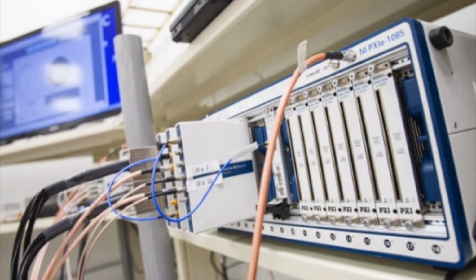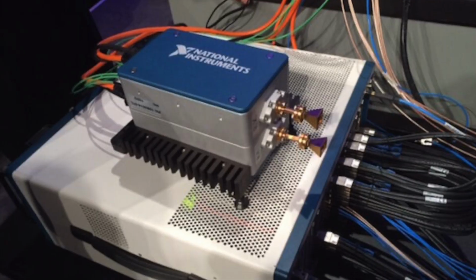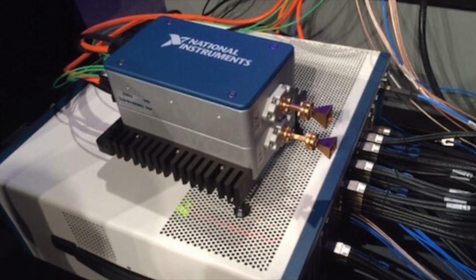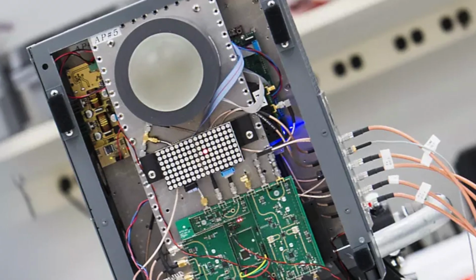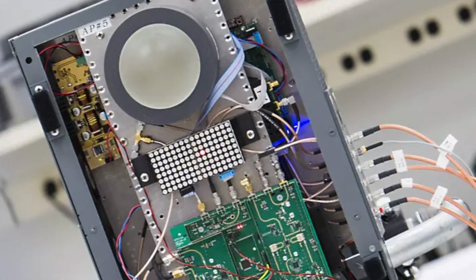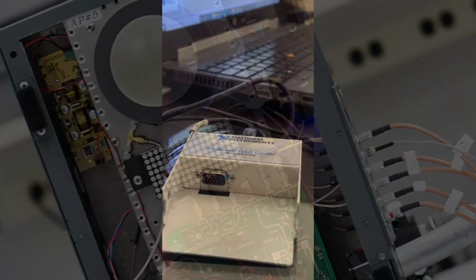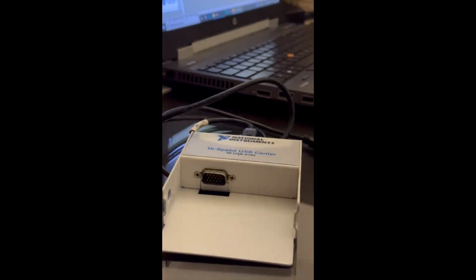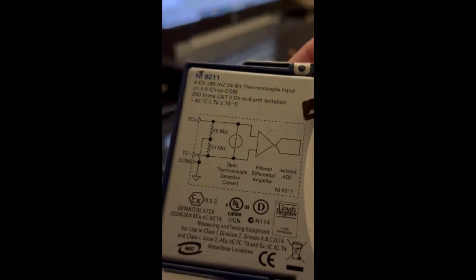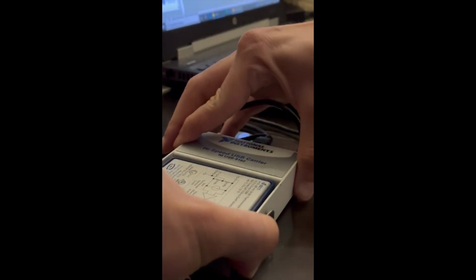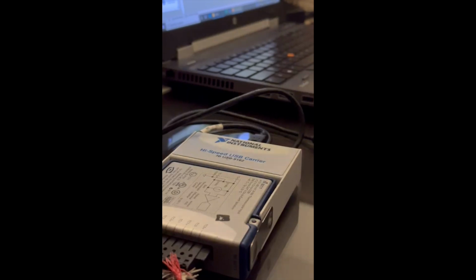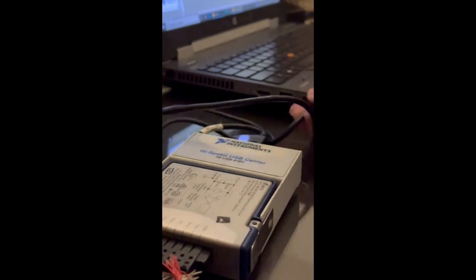Now, let me guide you through performing your first measurement using LabVIEW. I'm going to show you how to use the NI data acquisition device to acquire a temperature measurement using LabVIEW. In my system, I have a thermocouple module, NI 9211, which is connected to a single slot CompactDAQ chassis, and the single slot CompactDAQ chassis is connected directly to my laptop via a USB cable.